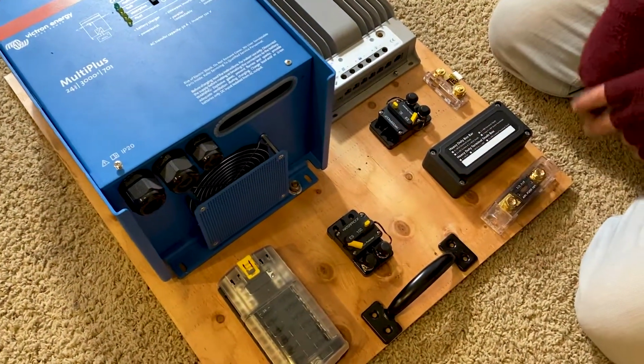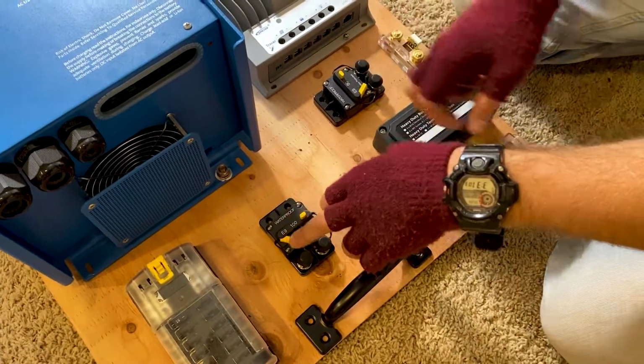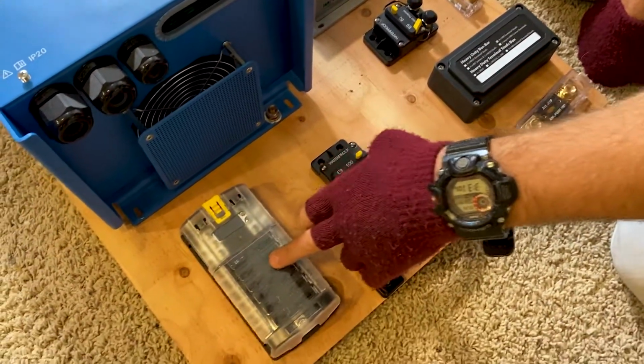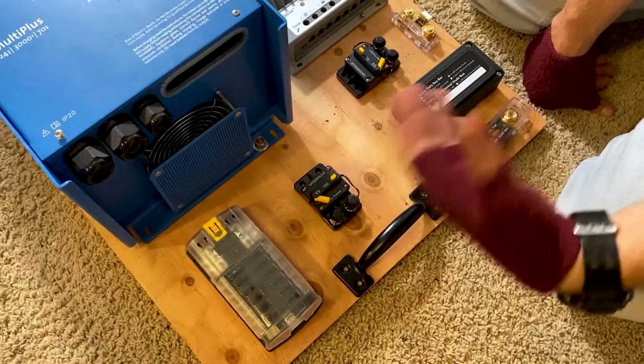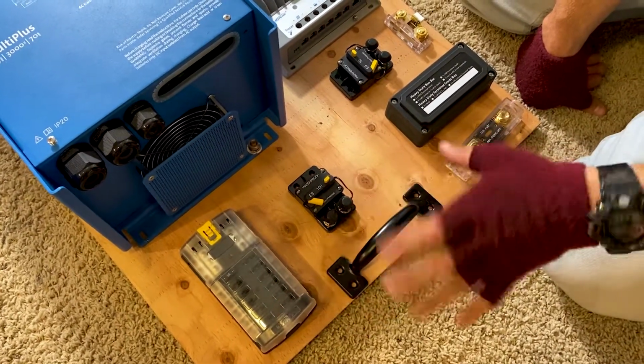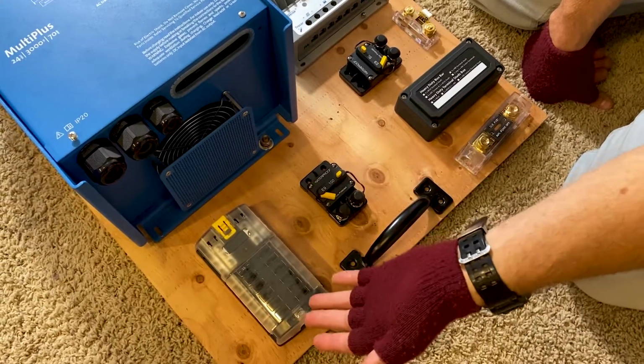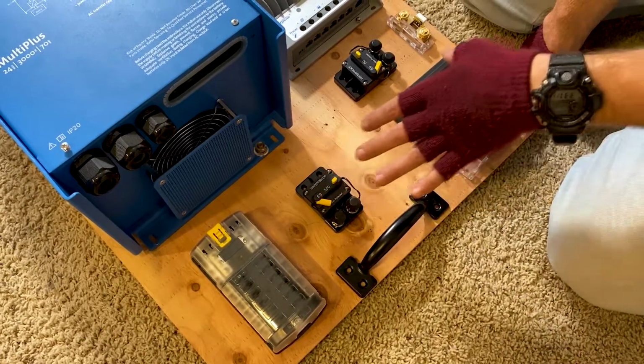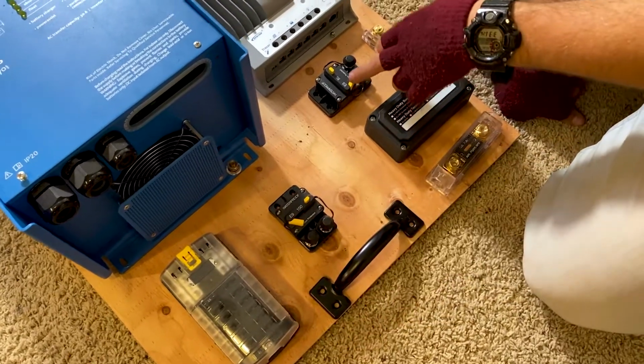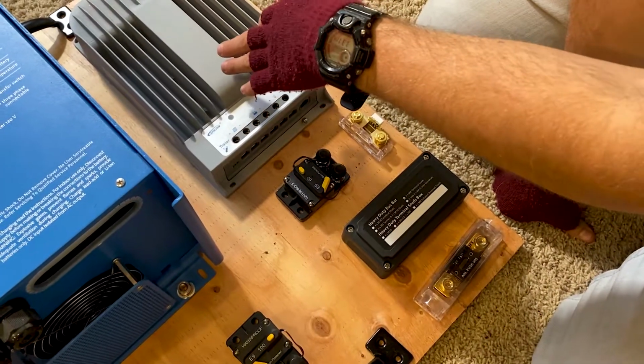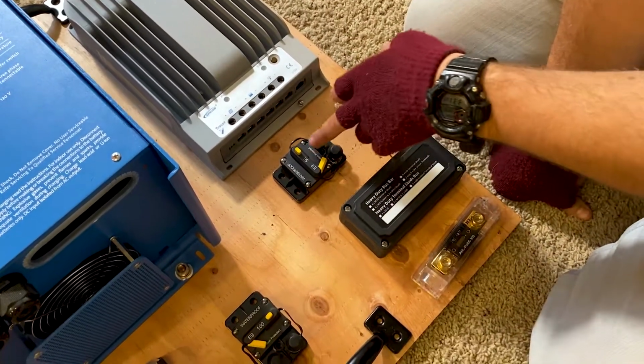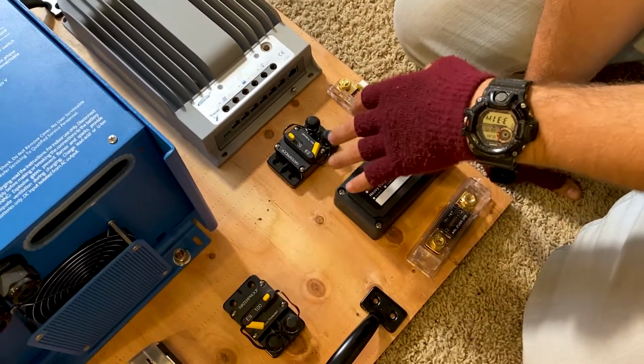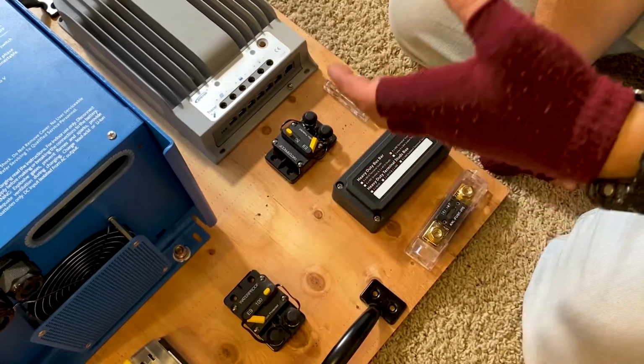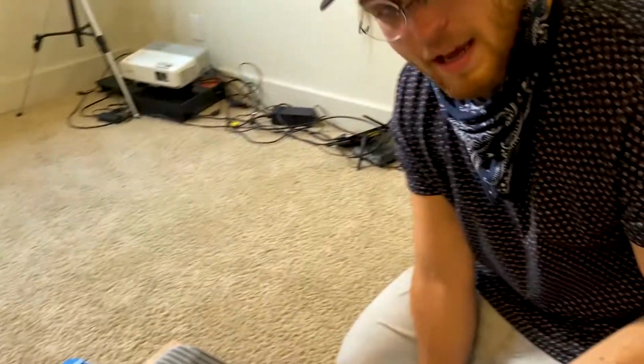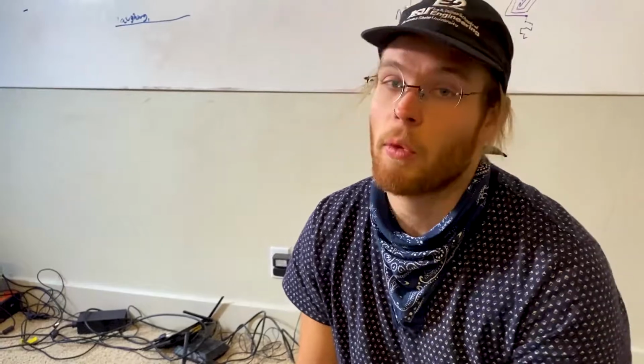Then these smaller components: we've got two circuit breakers. One is for our DC fuse block. Not 100% necessary, if there's too much amperage this will always just blow, but rather than blowing 15 small fuses, we'd rather trip a single circuit breaker, so it's nice to have this downstream. Then we've got our 50 amp circuit breaker for our 40 amp charge controller. If you're curious how we pick the sizes, you want about 1.25 times the amperage of the component you're protecting.